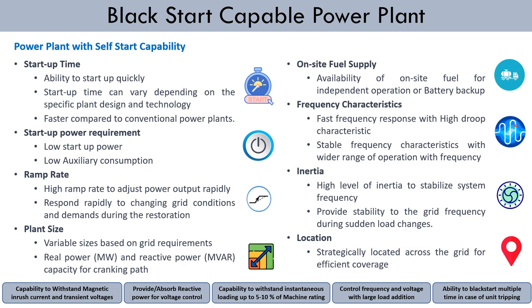Startup power requirement. Black Start Capable Power Plants typically have low startup power requirement due to low auxiliary power consumption. This helps in reducing the size of auxiliary power supply requirement system, including diesel generators or battery bank. Ramp rate. These power plants have a high ramp rate, which refers to their ability to quickly increase or decrease their power output. The ramp rate allows them to respond rapidly to changing grid conditions and demands during the restoration process.